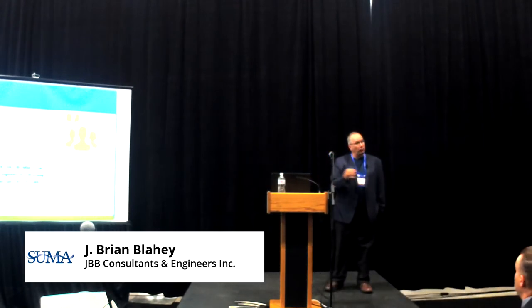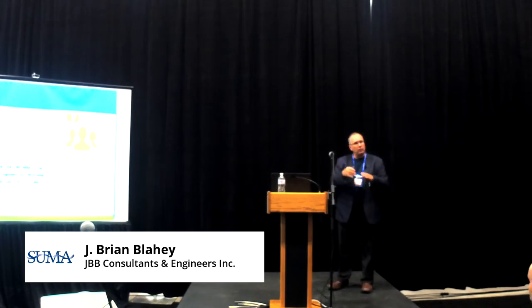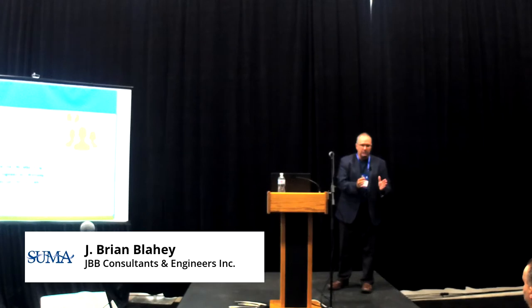First steps are to review what your viable options are for refrigerants, decide whether you want to replace the floor or reuse the floor. We talked a lot about here being new floor with direct. You can use CO2 with the indirect floor, but it's not as efficient. So then you have to sit there and say, okay, is my floor cracking? Is it 30, 35 years old? Is it time for a replacement? If you're at that stage, the direct is the way to go. But we would still go through that analysis to do that comparison.